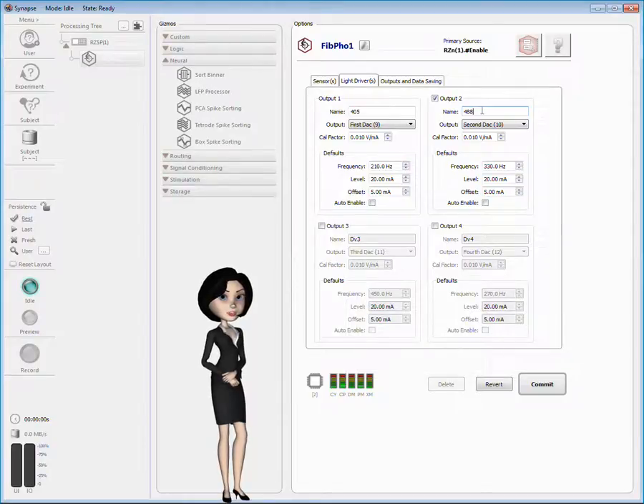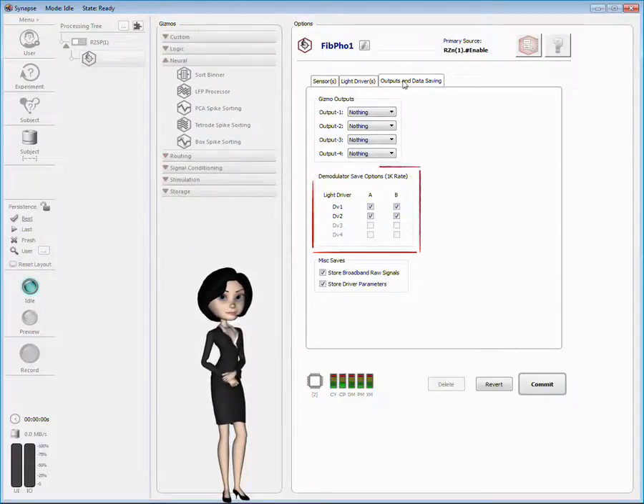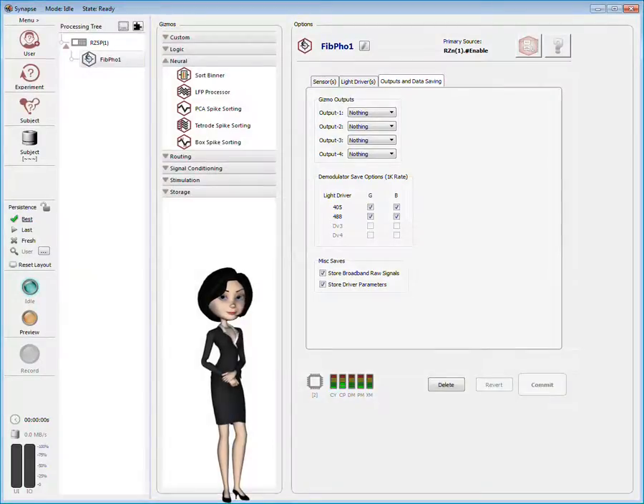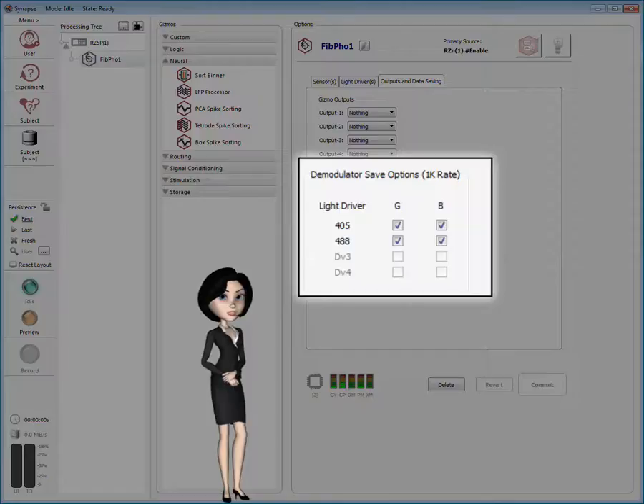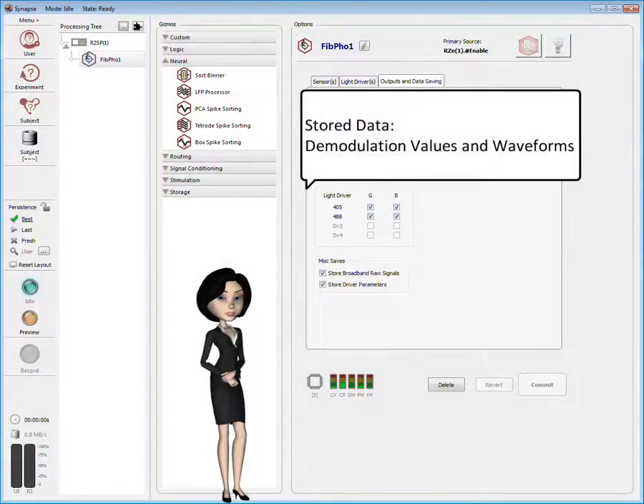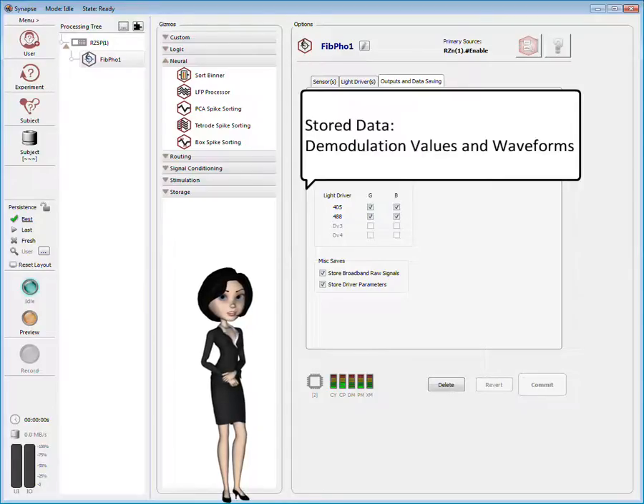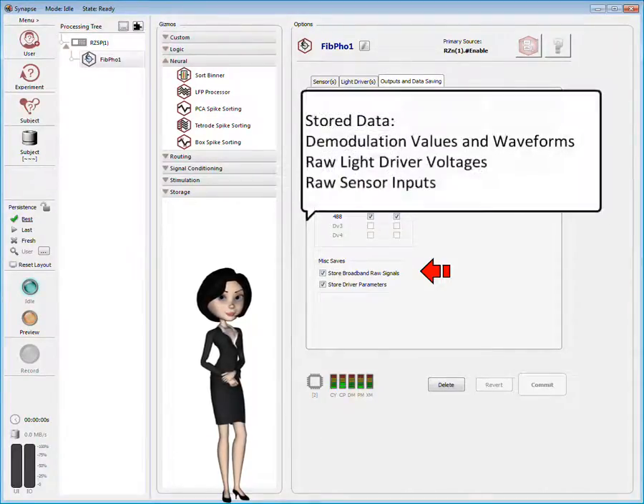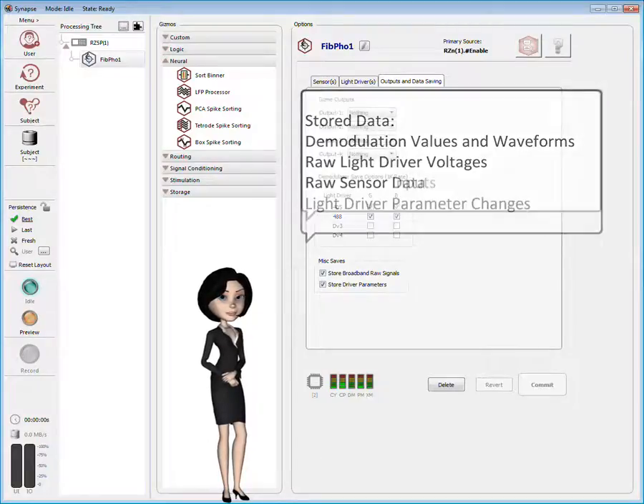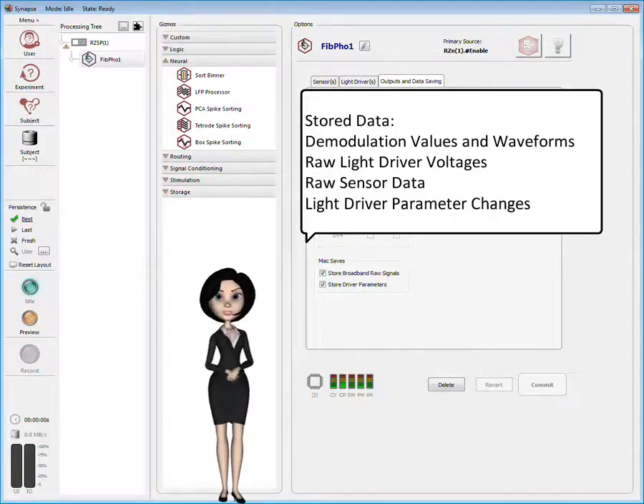Let's take a look at the final tab. On this tab, I can click the checkboxes in this matrix to select the combinations of sensors and drivers that will be used for demodulation. If I commit my changes so far, the table updates to show the new names I've given the sensors and drivers. The demodulation results from your selections are stored automatically, but you can choose what other information to save in the dataset. If you want to duplicate the demodulation with offline analysis, you'll need to store the broadband raw signals. They're made up of the raw light driver voltages followed by the raw sensor inputs. This option ensures that any changes you make to the parameters during the experiment are stored along with the other data.